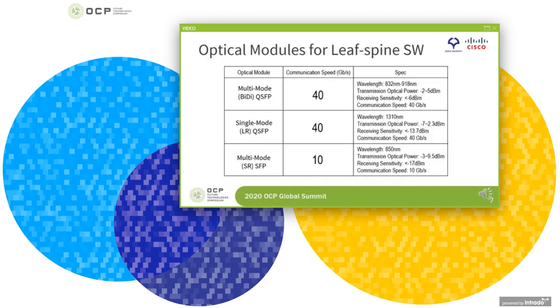The biggest challenge of liquid immersion cooling is securing communication performance of optical communication modules. So we examined them in 3 different settings, using a multi-mode module operated at 40 gigabit per second and 10 gigabit per second, and also a single-mode module at 40 gigabit per second.